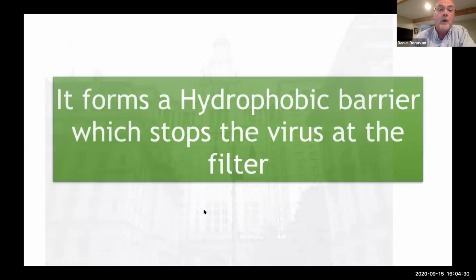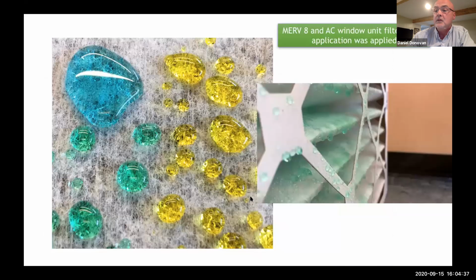So how does it work? Well, it forms a hydrophobic barrier, like I said, which stops the virus at the filter. If you look at the one on the left, that's a very cheap filter. You can see the weave pattern here, and this is water that's dyed. This is a photograph that they provided to us. But the one on the right, after I got a sample from them, we actually applied it to filters and tested it ourselves. And it does do exactly what they said it does. It forms a water barrier, a water seal, and the water just beaded and fell right off it. So that was pretty fascinating.